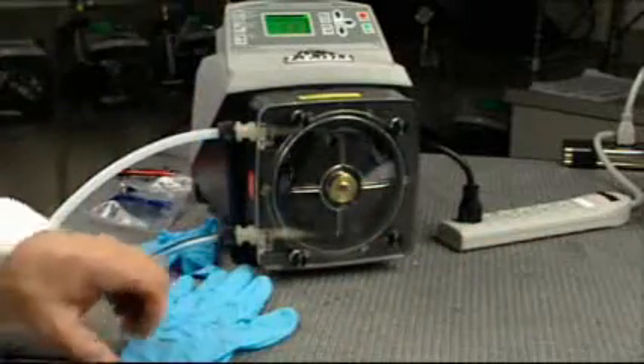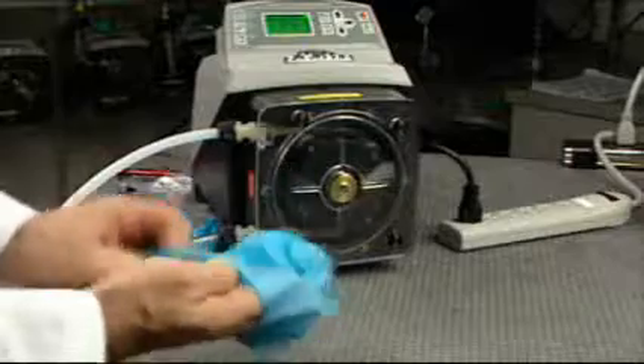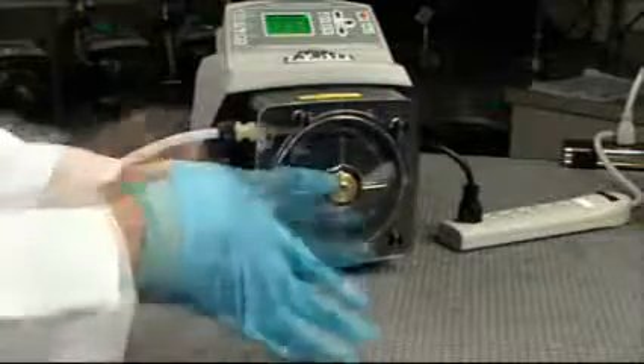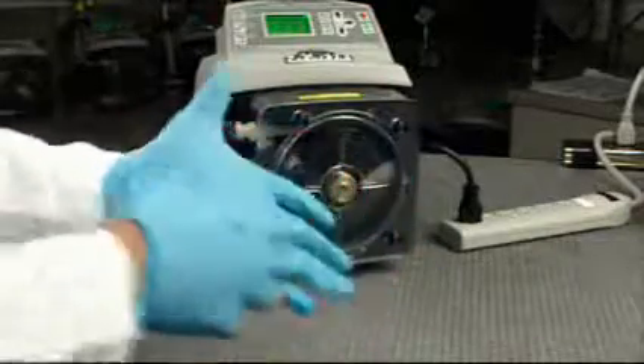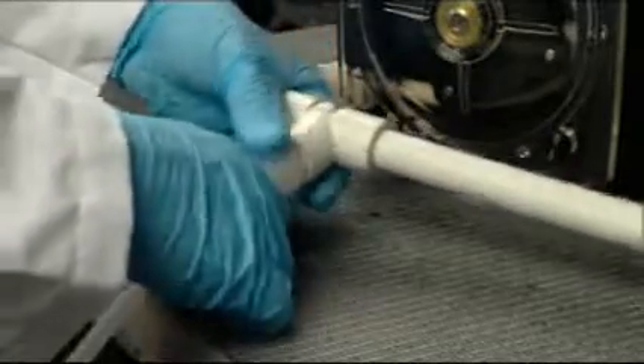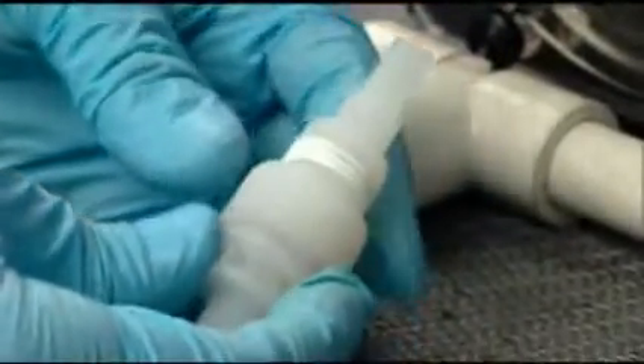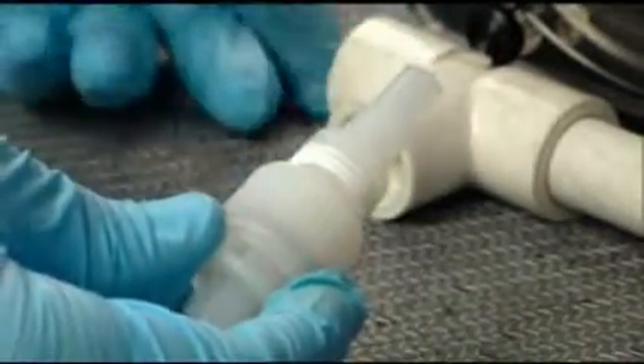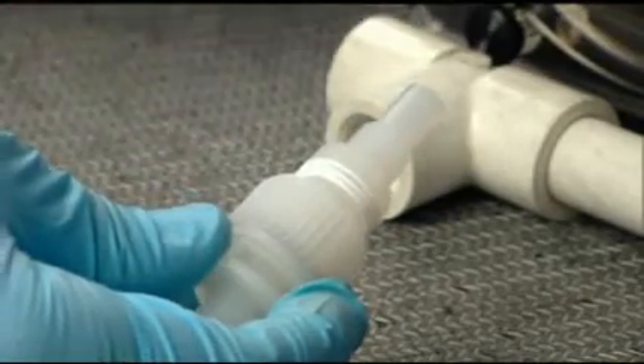Use caution when disconnecting the tubing. It may be under high pressure. Protective clothing and safety glasses should be worn while servicing the fitting. Be sure there is no flow or pressure in the piping system. Inspect the fitting for leaking or damage. Look for signs of material fatigue, such as stress cracks, discoloration, or brittleness in the plastic. The entire fitting should be replaced if damaged.